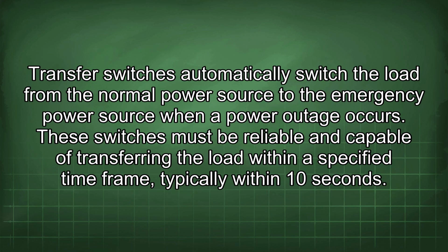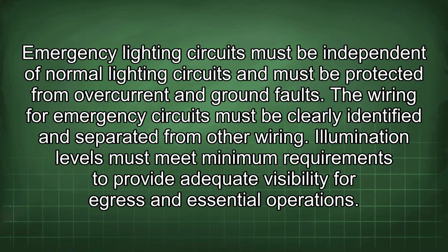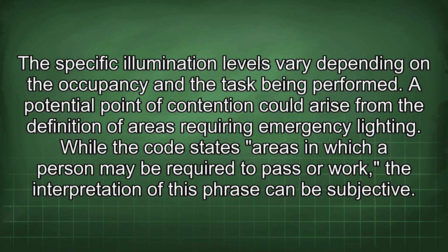Transfer switches automatically switch the load from the normal power source to the emergency power source when a power outage occurs. These switches must be reliable and capable of transferring the load within a specified time frame, typically within 10 seconds. Emergency lighting circuits must be independent of normal lighting circuits and must be protected from overcurrent and ground faults. The wiring for emergency circuits must be clearly identified and separated from other wiring. Illumination levels must meet minimum requirements to provide adequate visibility for egress and essential operations. The specific illumination levels vary depending on the occupancy and the tasks being performed.